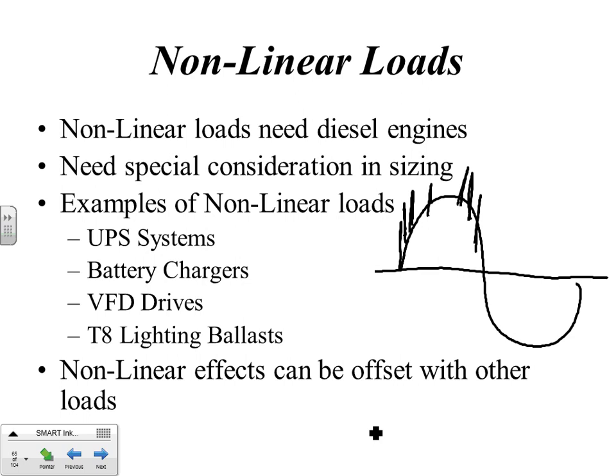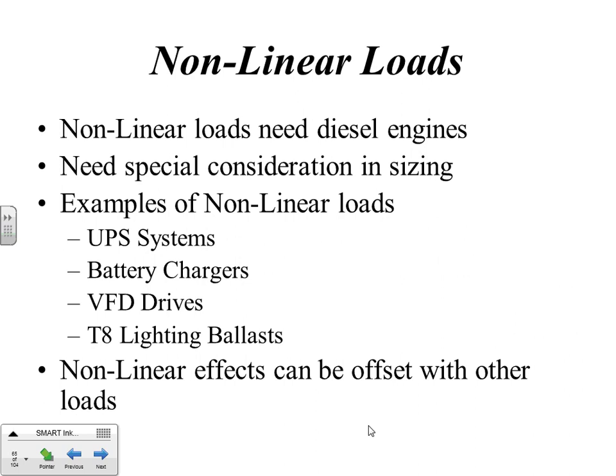Well, we offset that by putting different types of loads. We wanted to get rid of as much of the notching on that wave as we could. So I brought a load bank with me, and I told them also to connect some air conditioning to it before I got there. And air conditioning was just a regular motor. It wasn't a nonlinear. And the addition of those loads against the bringing up the linear load with the nonlinear kind of damped out the effects of those spikes and took the problem away. So the bottom line was, they just put some more linear load on the whole system, and that fixed it.